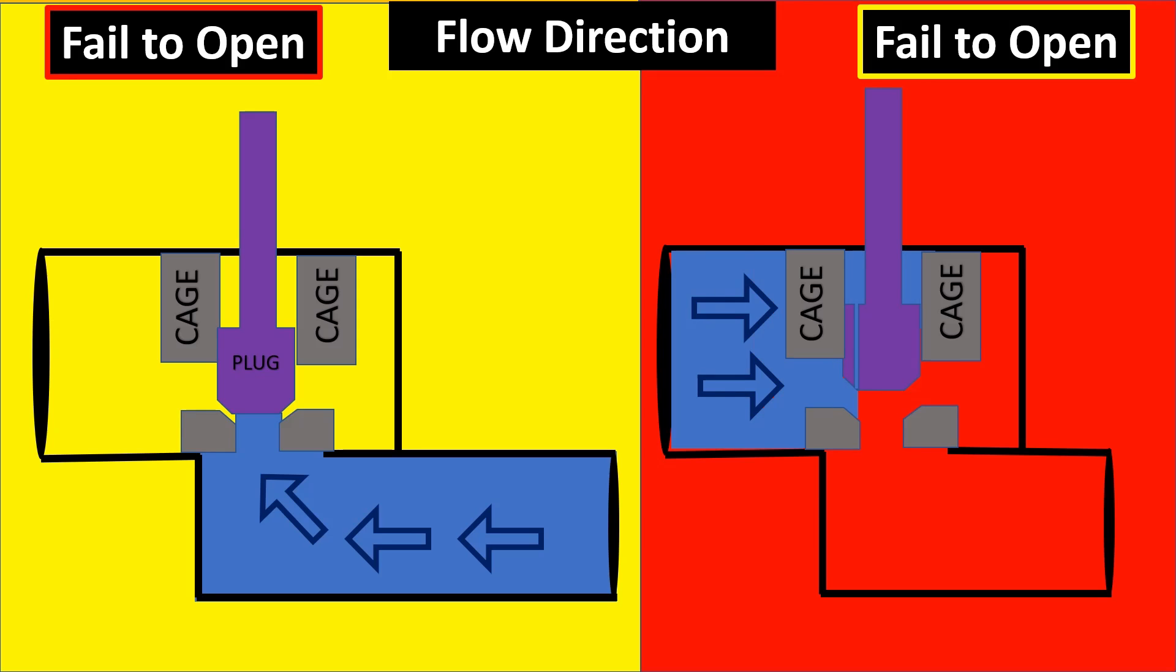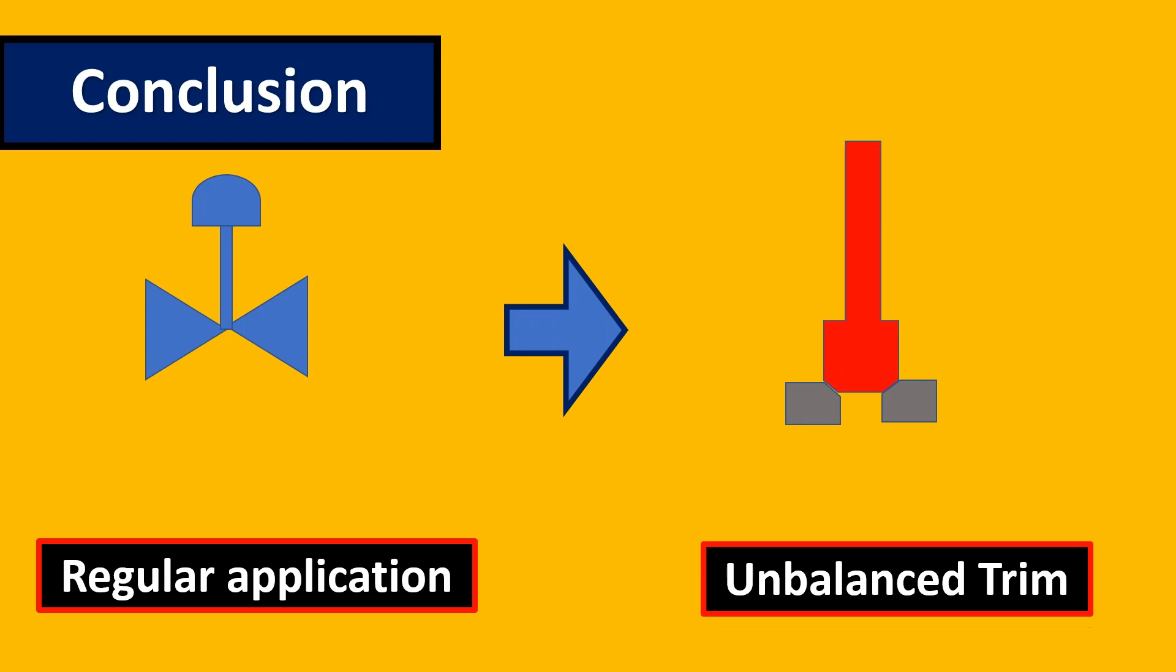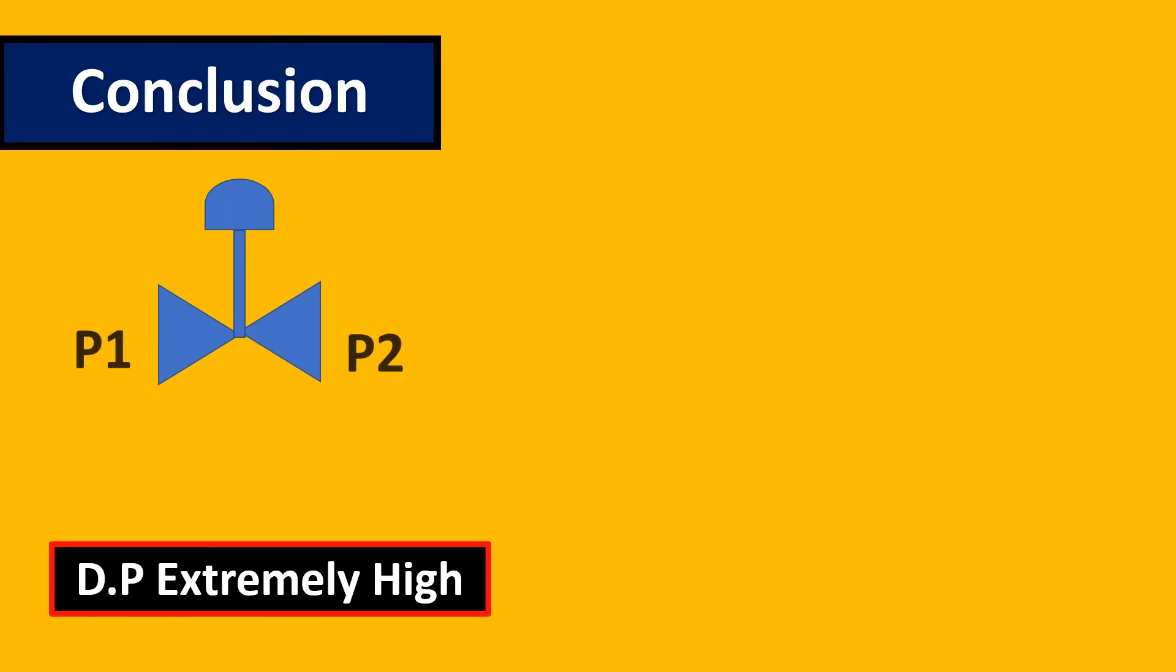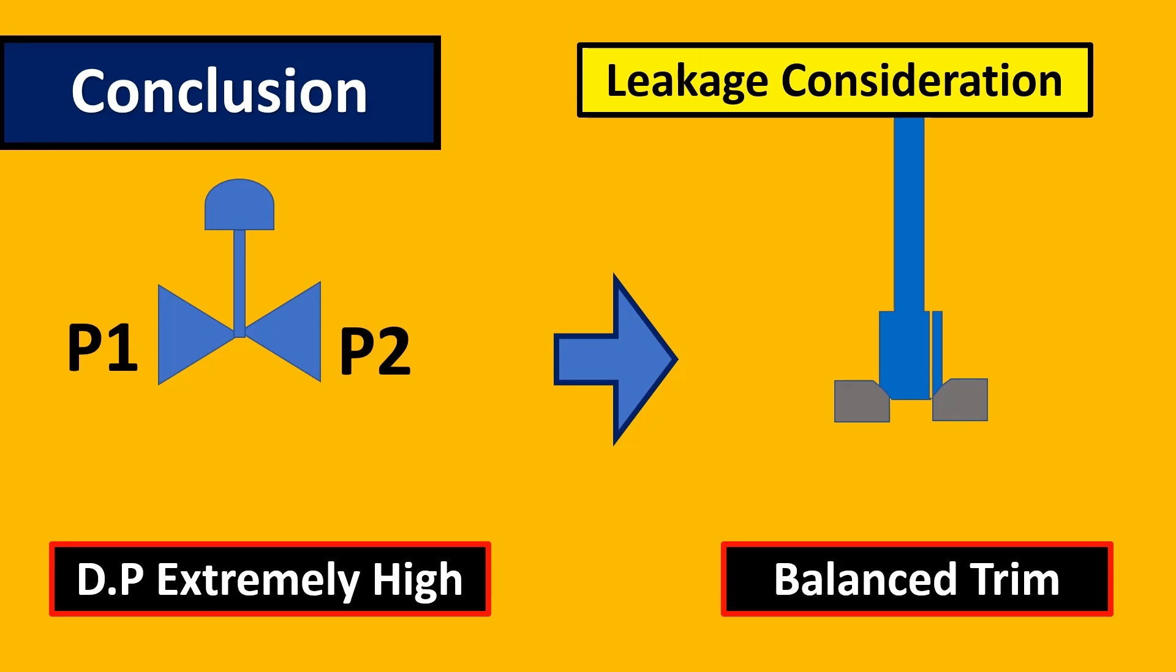Now the final verdict: when to use what? In a regular application, you would usually go for an unbalanced design—almost 90 percent of your applications—because of the leakage considerations. If you have extremely high DP and you might not want an actuator with such high torque, then you would go for a balanced trim in this case, where you are okay with the leakage considerations.